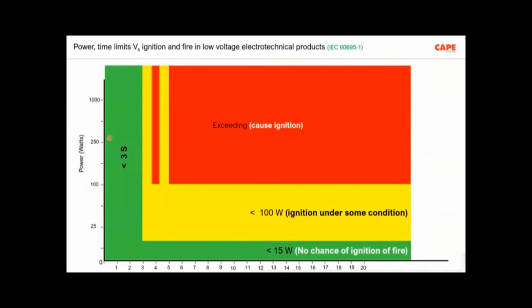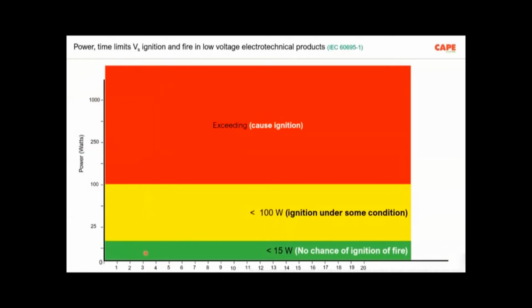So if the power rating is lesser than 15 watts, the chance of ignition of fire from that particular equipment is lesser. Between 15 to 100 watts, it may or may not create fire. More than 100 watts, of course, it's dangerous. Also, the peak power is not limited to 1000 watts, I have put 1000, but it can be even higher. A device can even be 2 kilowatt, 3 kilowatt, 4 kilowatt.